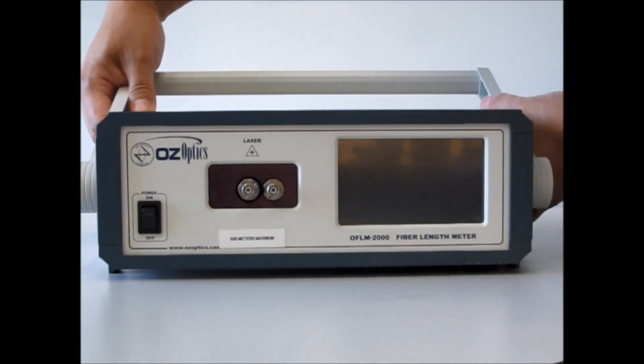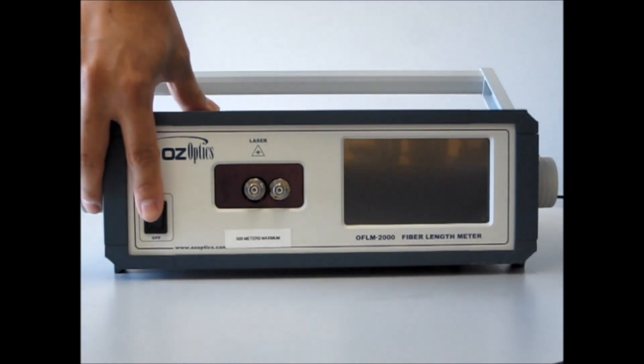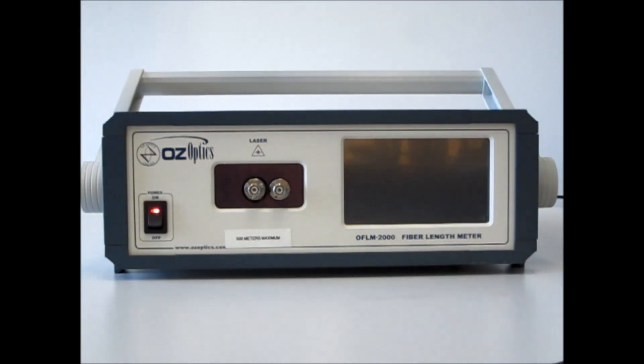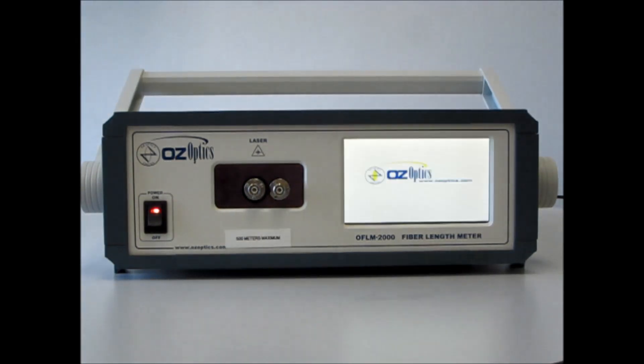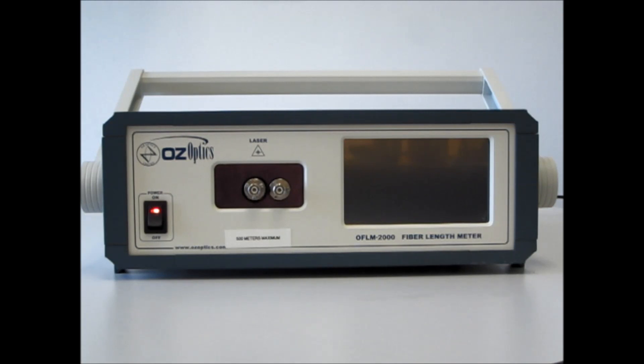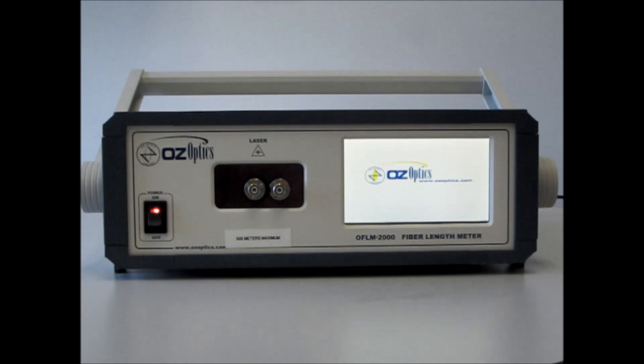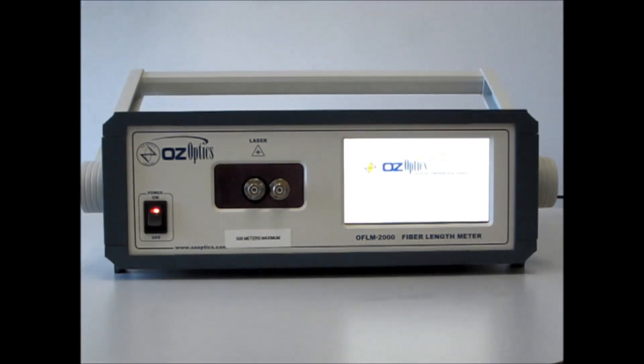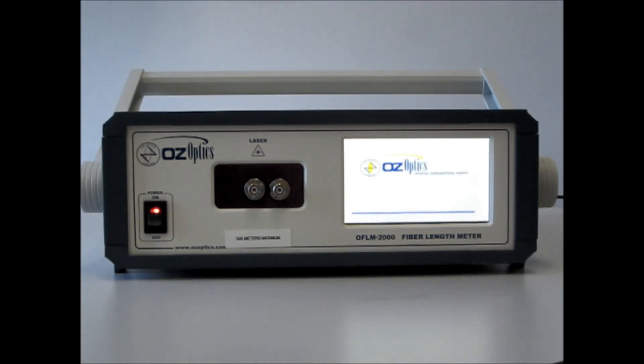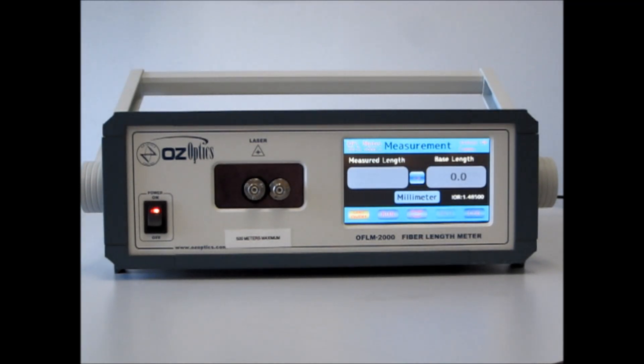Pick it up, turn it around, and turn the power on. The unit boots up, performs some diagnostics, and an internal systems check. Once this screen is displayed, the fiber length meter is ready to use.